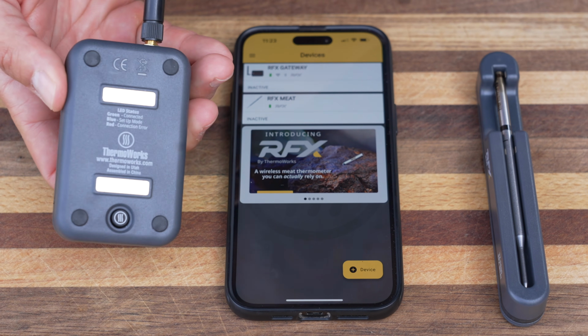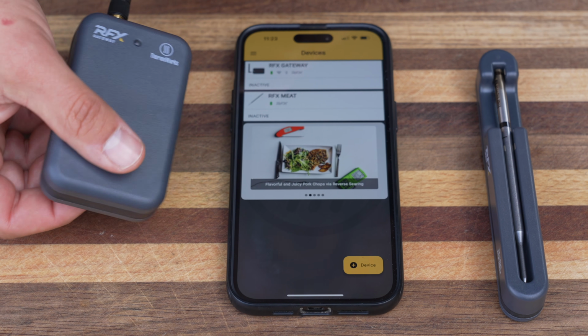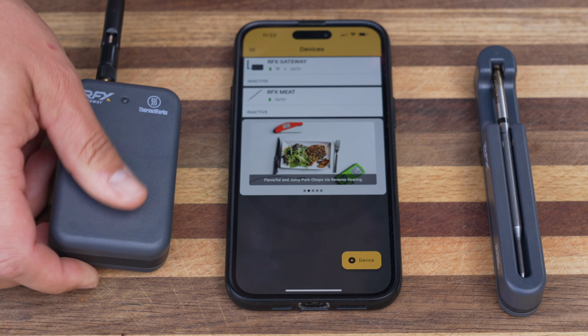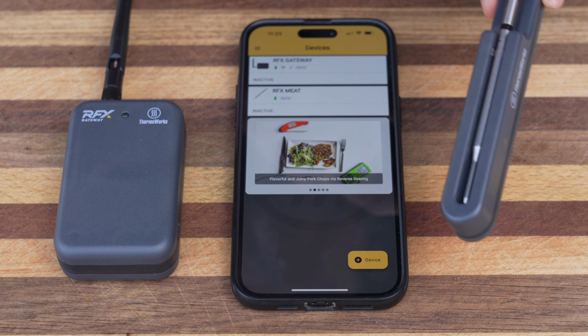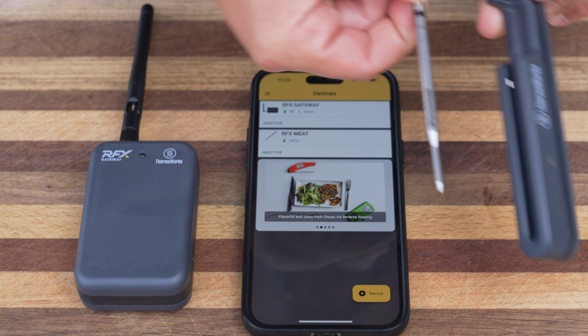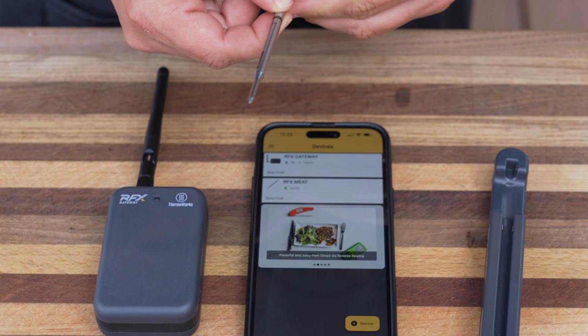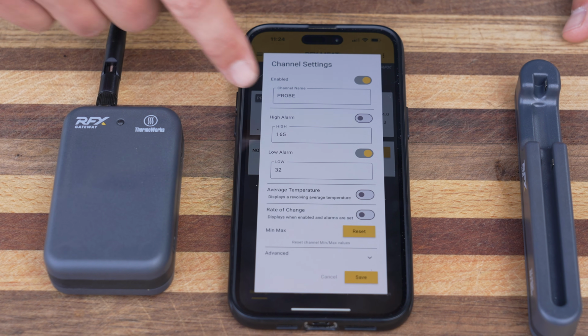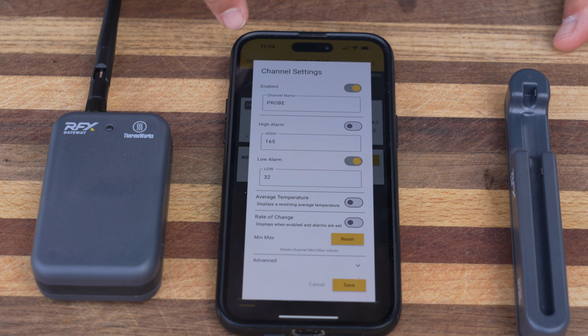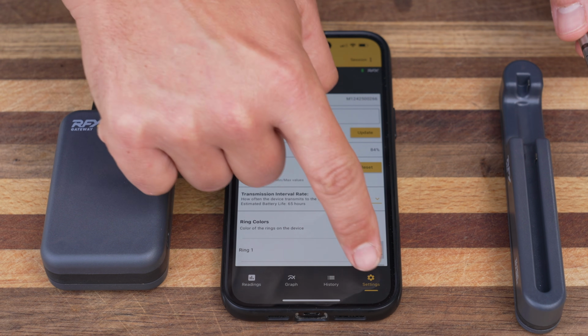And to turn everything on, there is a button on the back of the gateway. You press this, and this will connect and wake everything up. And in order to turn on the wireless sensor, you just remove it from the cradle, and this thing is ready to go. You can adjust your high and low temperature alarms right here within the channels tab. Another important setting is within the settings tab.